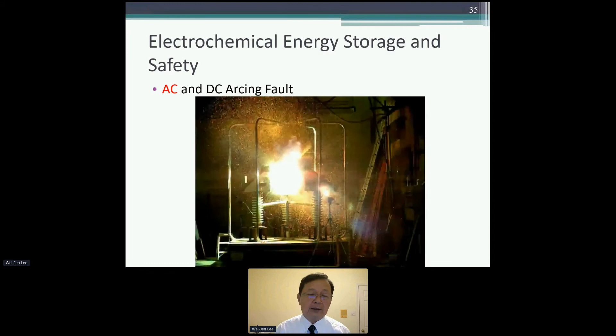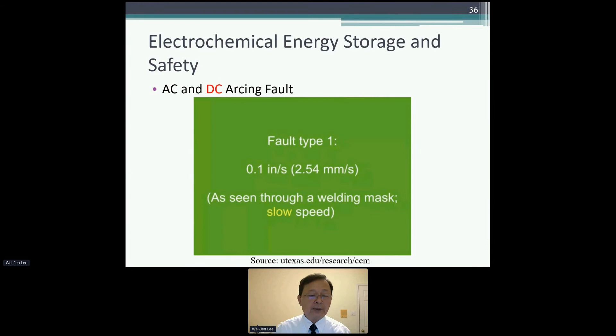This is one of the tests I performed in the lab, looking at the AC arcing fault. This is the slow motion video. You can see for the AC fault, you have a zero crossing. However, for the DC fault, you don't have a zero crossing.